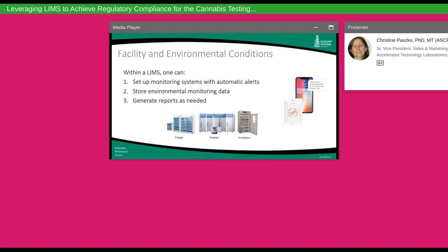Additional resource requirements include facility and environmental conditions. Within a LIMS, one can manage different facilities and set up monitoring systems with automated alerts where thermocouples are placed in refrigerators, freezers, and incubators. If temperature goes above a limit, an email or text message can automatically be sent, and you can have real-time temperature updates with monitoring over time. You can also generate reports on the equipment and share them with the metrology team as required.